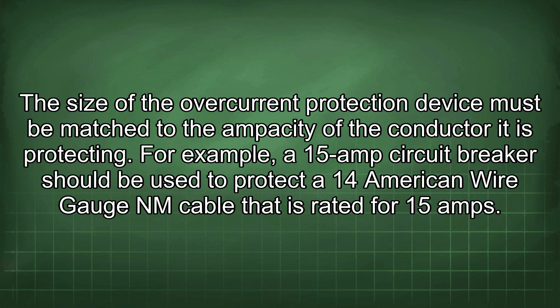For example, a 15 amp circuit breaker should be used to protect a 14 American wire gauge NM cable that is rated for 15 amps. It is important to never install an overcurrent protection device that is larger than the ampacity of the conductor it is protecting. This can create a dangerous situation where the conductor can overheat and potentially cause a fire.